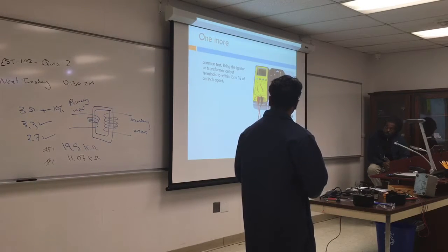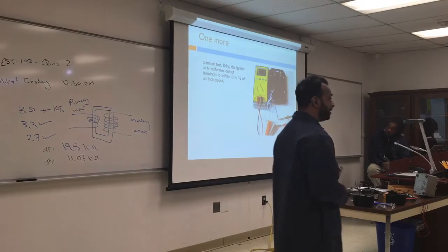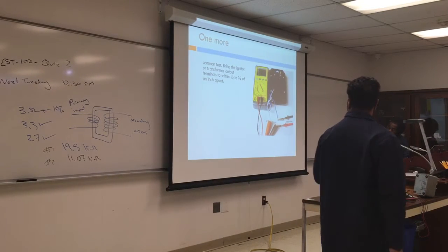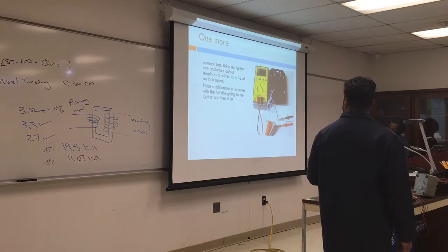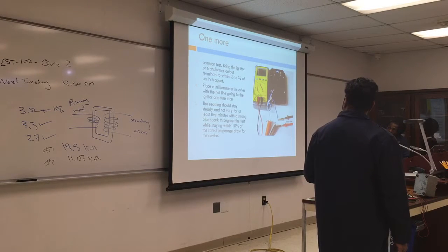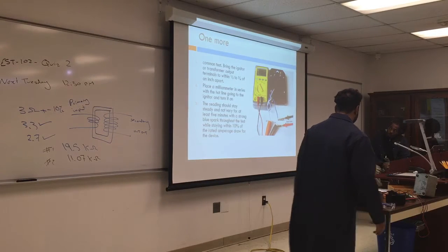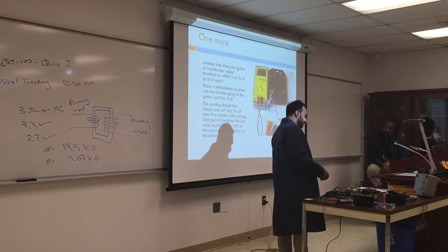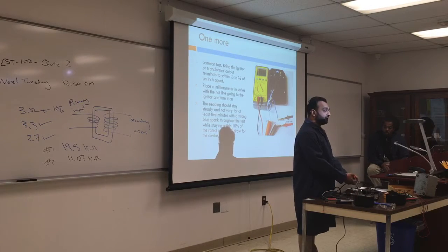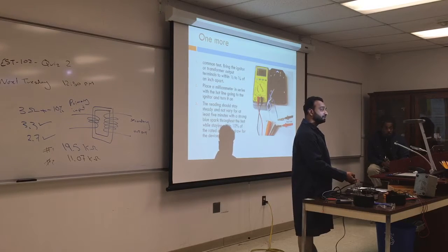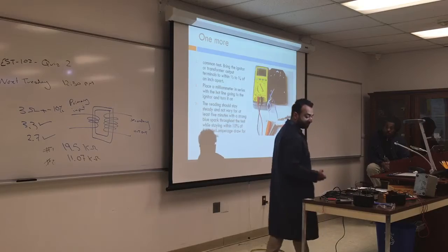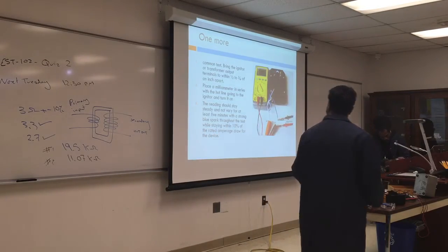Another method you can use is turn it on, leave it on, and put a clip-on meter on it. The amperage should not change. So the summary of all this is you turn it on and put a clip-on meter and watch for the amperage drop, leave it on for 10 minutes. If the amperage does change, what does that mean? This transformer is not good because it's changing amperage as it heats up. 5 minutes should give you an answer.